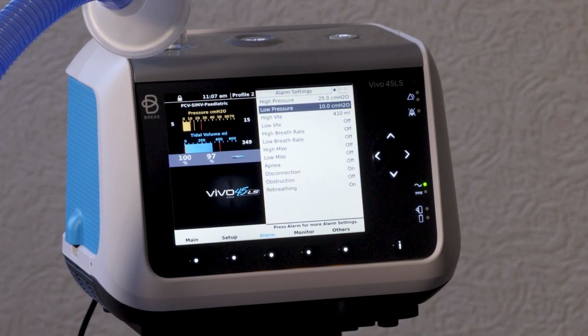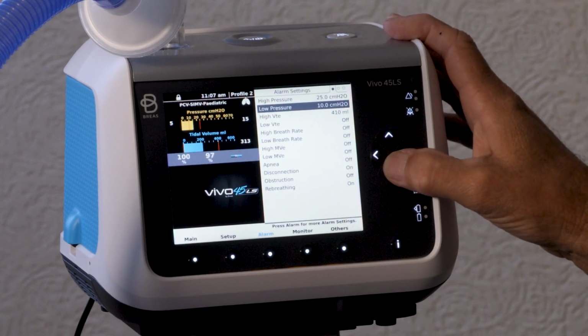And then you want to work your way on down, make sure that there's good integrity throughout the whole circuit, from the patient to the water chamber and the water chamber to the ventilator. Okay, so that's how you troubleshoot a low pressure alarm.